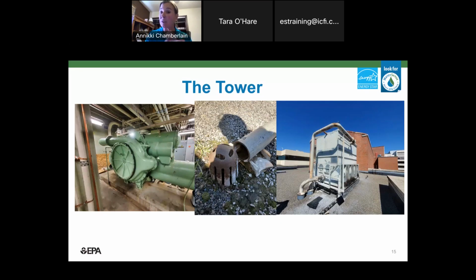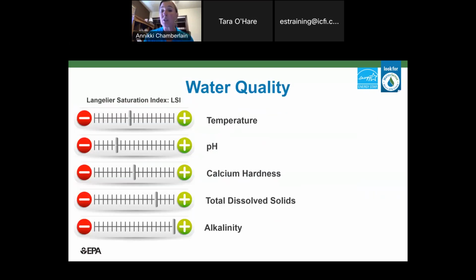But when I looked at the service report, I saw that the chemical concentration was very high for this tower. So I thought, well, if we have a constant flow, maybe that's something that we could adjust. Even if the tower is not perfect, it's still going to have its own optimal. It's like people, each a unique person with unique needs. It just depends on the operating conditions in the tower.